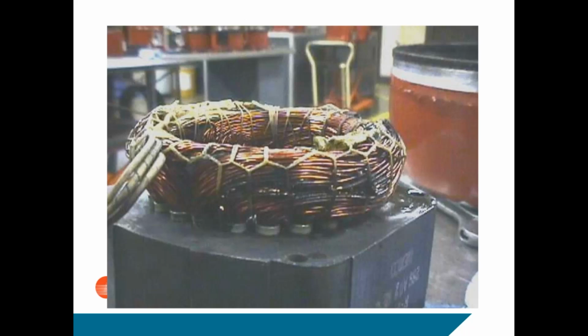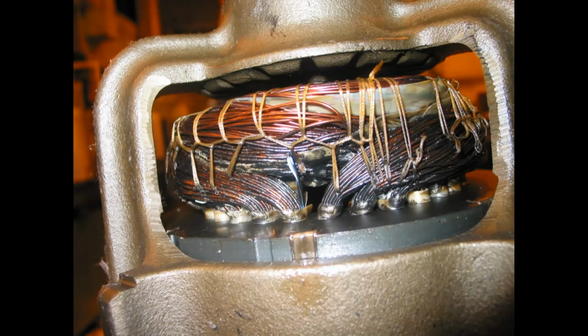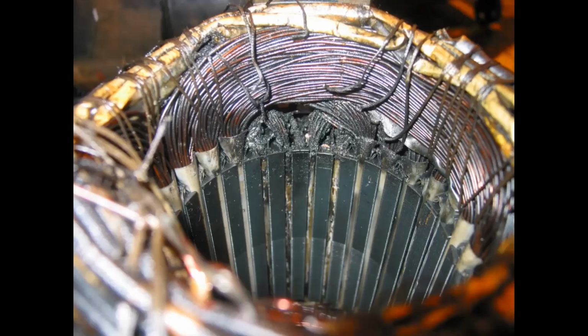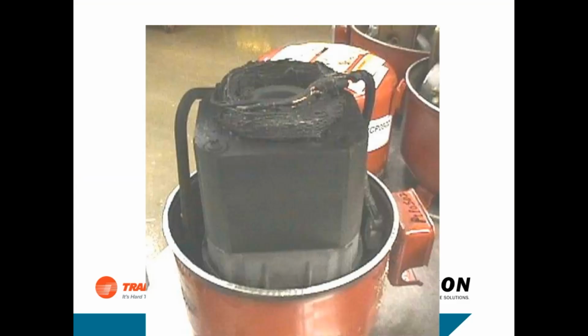This is a start winding failure on a compressor. I don't know if anybody's ever seen the internal of one of these, but that's basically what the motor looks like with a start winding that burned out. And again, start winding burnout could be a stuck potential relay, could be almost anything. Again, another picture of a winding burned out. This is what the inside of the motor looks like, the rotor or the stator part of it. There's another burnout.